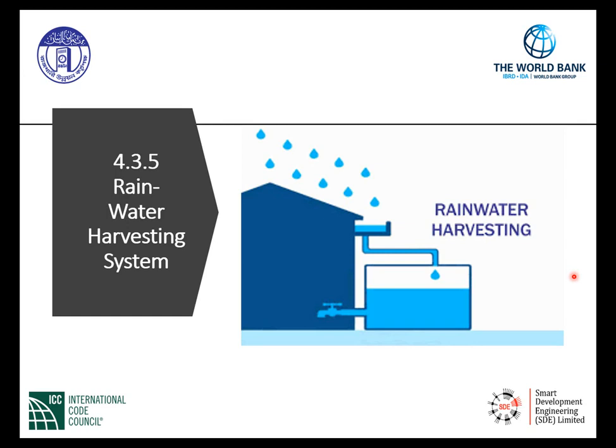So the other thing that this is telling us is that we need to size that reservoir capacity correctly. It says the reservoir capacity has a size requirement where the code states that it shall be a multiple of the area of the ground coverage of the building and a rain collection coefficient of 0.073. So what is the ground coverage of the building? Let's come up with an example: let's say that is 100 meters squared, just for ease of calculation. So we have 100 meters squared of ground coverage of the building times the rain collection coefficient of 0.073. That tells us you come up with 7.3. So I need a reservoir capacity of 7.3 cubic meters.